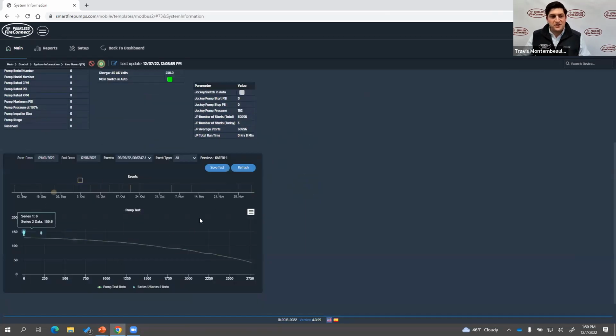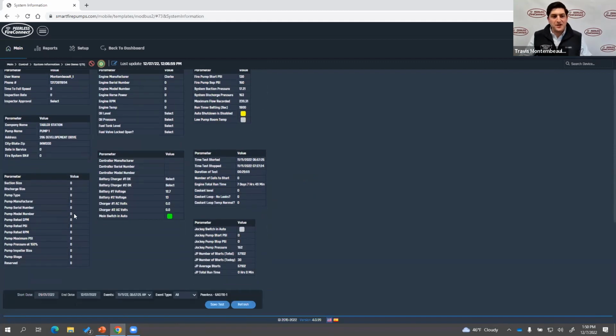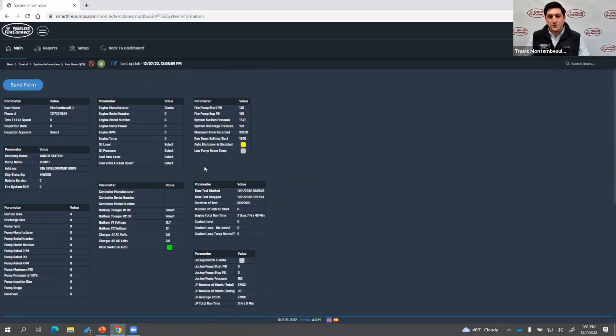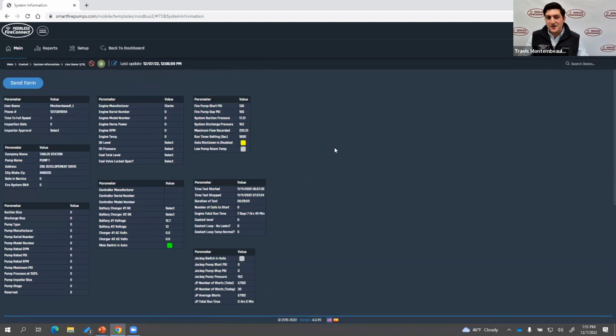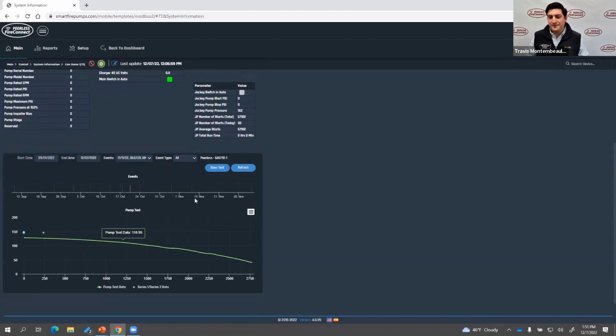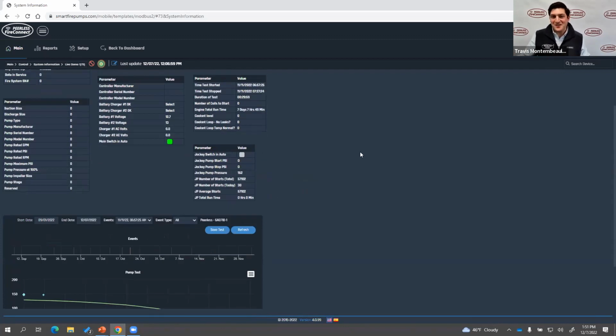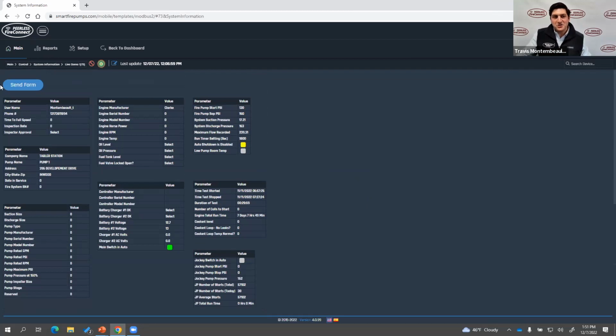And just from an output standpoint, we have the curves down here that are available. So as you choose your curve, say, I need to see my test from November 11th, you can select it. We've got pre-configurable fields all around here, data standpoint, battery voltage, and you can check the boxes to say, okay, the voltage was okay. I checked oil level and oil pressure. Those were okay. Those are visual indicators that people check when they're on site, so check those boxes, and then you can output right there as well. And same deal, Drew, this data could be sent to an ITM platform like InspectPoint. And so when you're doing that test, these fields all pre-populate, so you're simplifying that inspection for whoever's doing it.